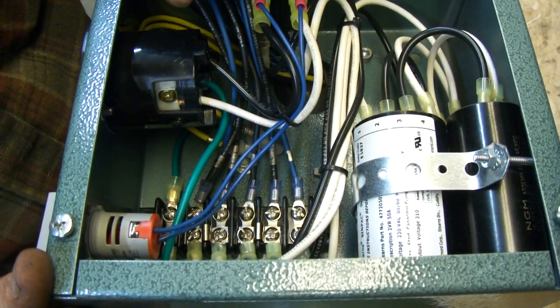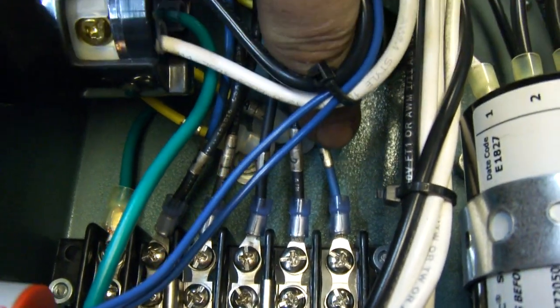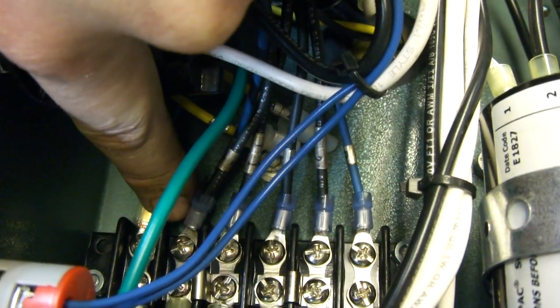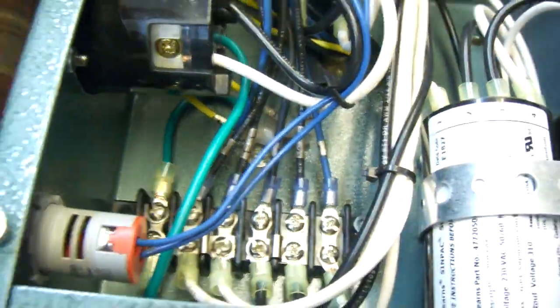Now if the motor runs backwards, you'll reverse the two blue wires. You'll move this blue wire onto this terminal with the number two wire and move this blue wire over onto this side, top side.